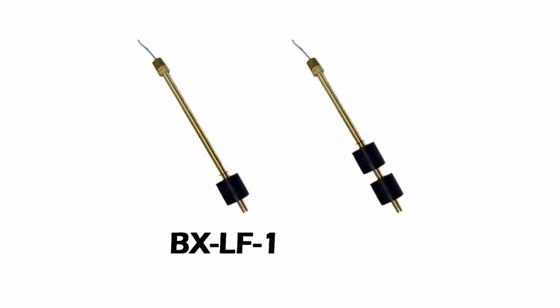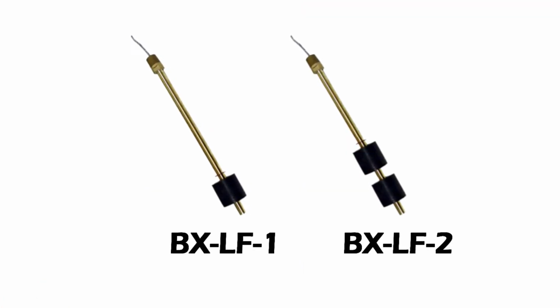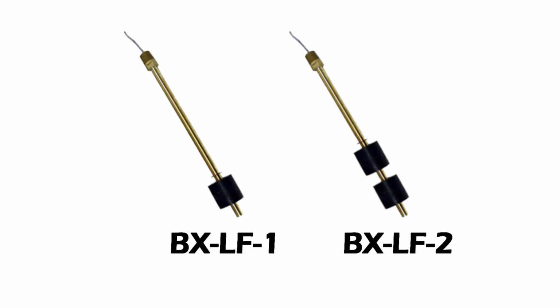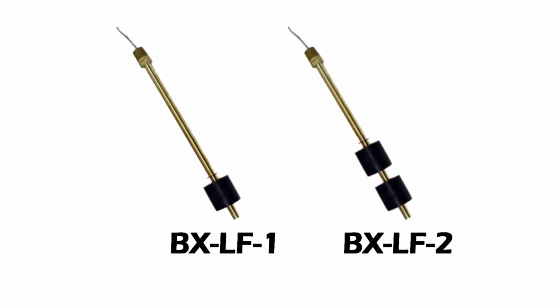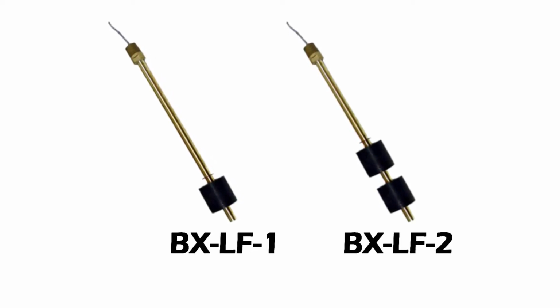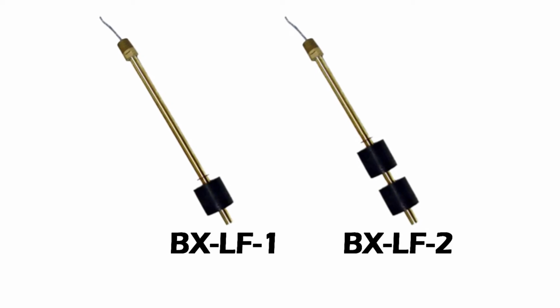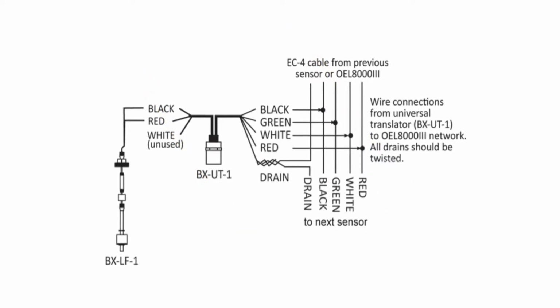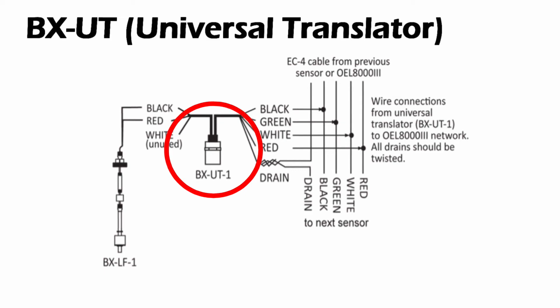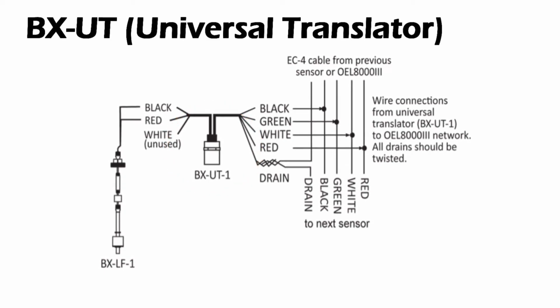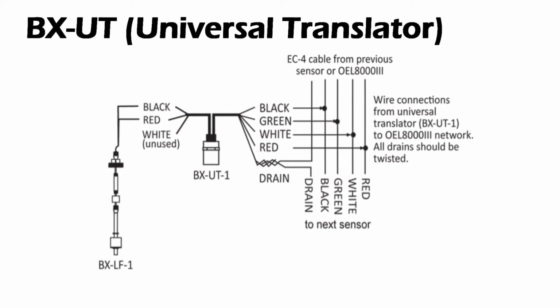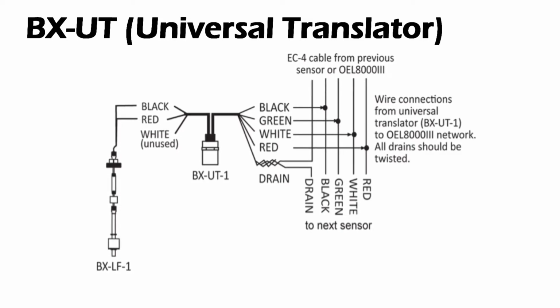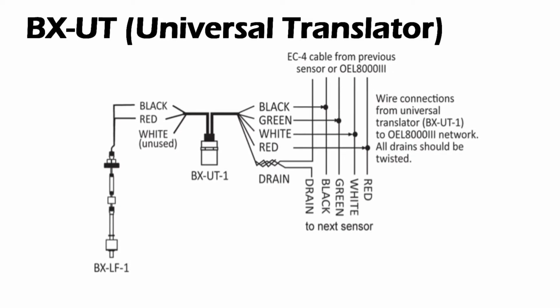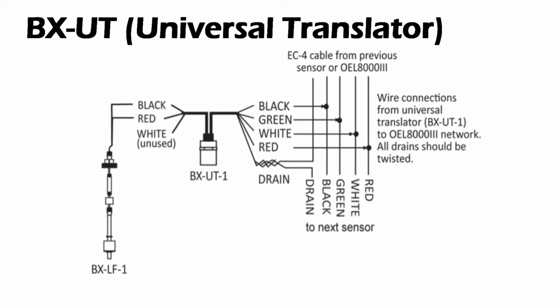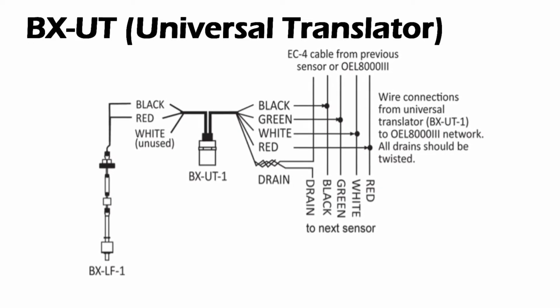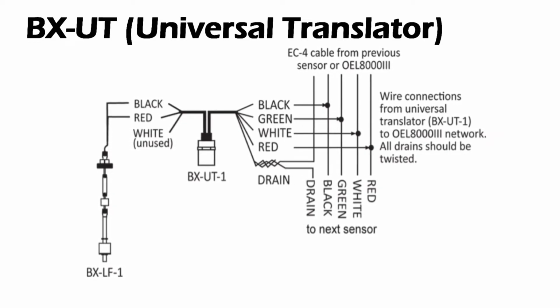The BXLF1 and BXLF2 are non-optical level float sensors. These sensors offer multiple options including float material, float sizes, and mounting options. The BXLF sensors require the use of a BXUT, or universal translator, to convert a dry contact switch closure to an electric signal that the Proteus controller can recognize. The BXUT can also be used to connect non-OMNTEC float sensors to our Proteus controller.